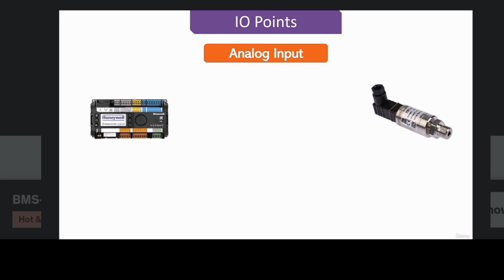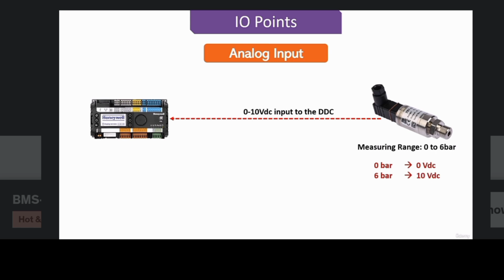Let's understand an analog signal with an example. A water pressure transmitter measures the value of pressure and converts this pressure value into a 0 to 10 volt signal. DDC reads this electrical signal and converts it again to the pressure value using already defined criteria inside the DDC. If this pressure sensor measuring range is 0 to 6 bar, then 0 pressure will be represented by 0 volts, and when pressure is 6 bar, then the transmitter will send a 10 volt DC signal to the DDC controller. The same configuration will be done inside the DDC controller during the programming. So the DDC controller will know what the pressure value is based on the electrical signal it receives. For example, if the DDC controller receives a value of 5 volt DC, then it will know that the pressure value is 3 bar.